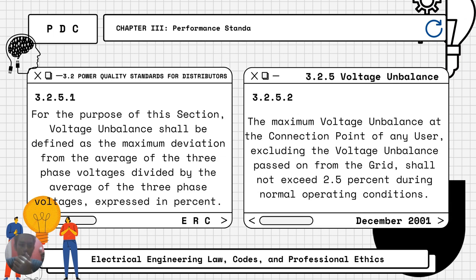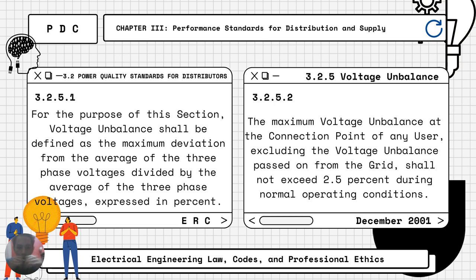Moving on to voltage imbalance, another part of power quality standards for distributors. Voltage imbalance shall be defined as the maximum deviation from the average of the three phase voltages divided by the average of the three phase voltages, expressed in percent. The maximum voltage imbalance at the connection point of any user, excluding the voltage imbalance passed on from the grid, shall not exceed 2.5% during normal operating conditions.